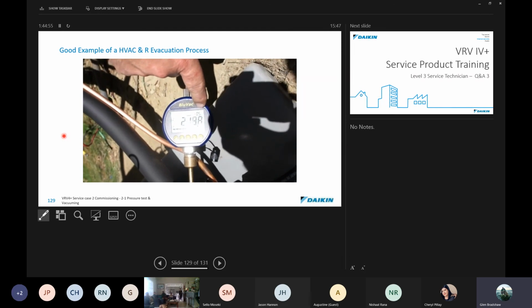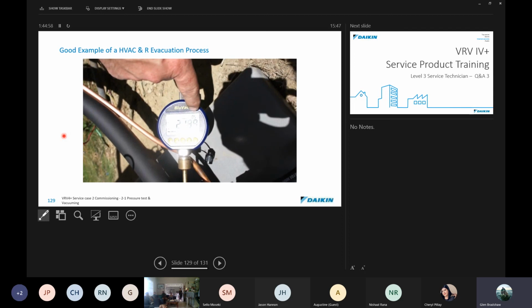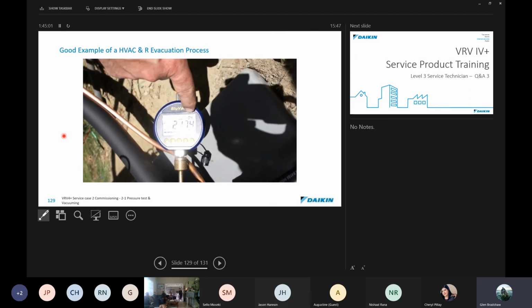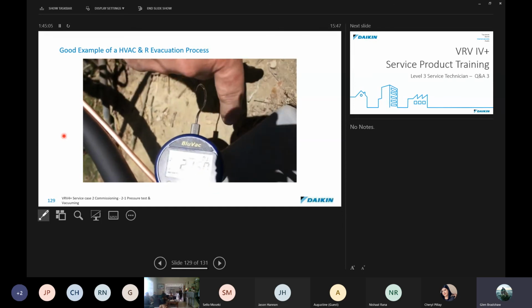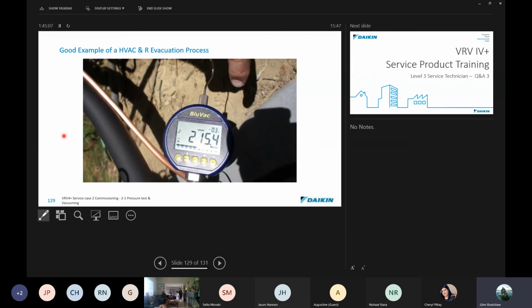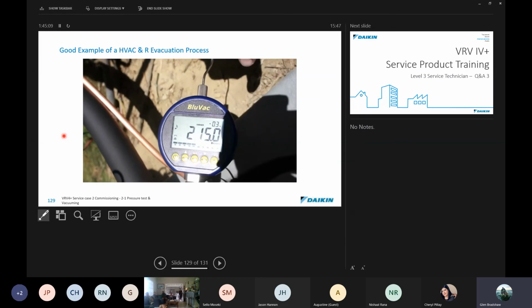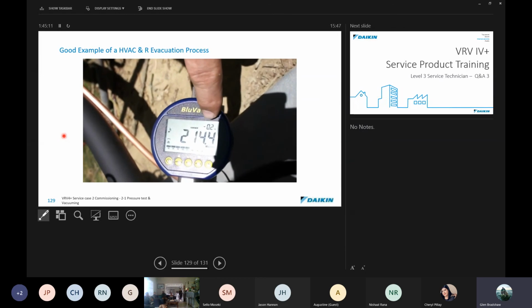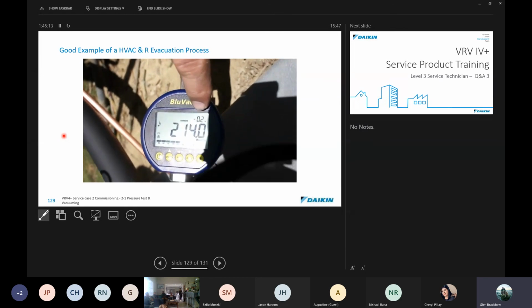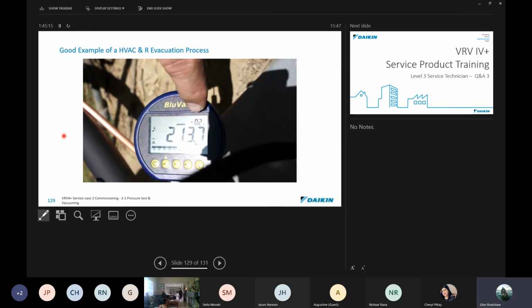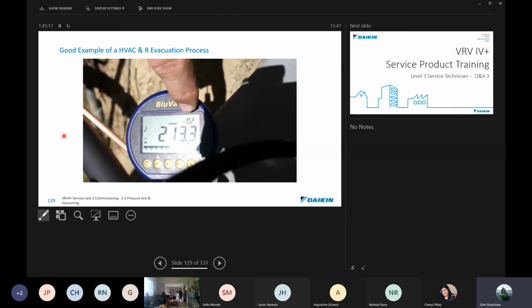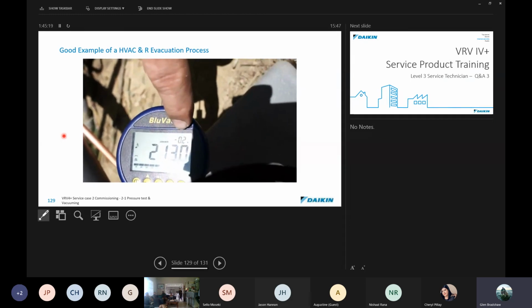See our leak rate indicator showing we're at about 0.6 microns per second. So, you know, it's slowing down, and that's to be expected. The deeper the vacuum gets, the harder it is to pull. So we're at 216, 15, 14. You can see that's still dropping off. That's exactly what we'd expect to see. The deeper the vacuum gets, the slower we're going to go.